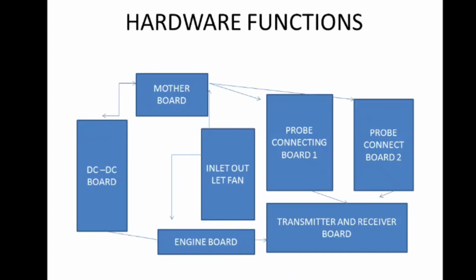What is this probe connecting board 1 and board 2? I said a term called port, right? This port is connected directly to these hardware functions. Whenever you fix a probe, it will be connected towards the motherboard, and with that help you can see the entire image. There are a few other boards included in this, like the continuous wave board and the 4D board. The continuous wave board comes into function only if there is going to be an echo process. If there is no echo process, that machine won't have a continuous wave board at all. You need not fix that board at all.